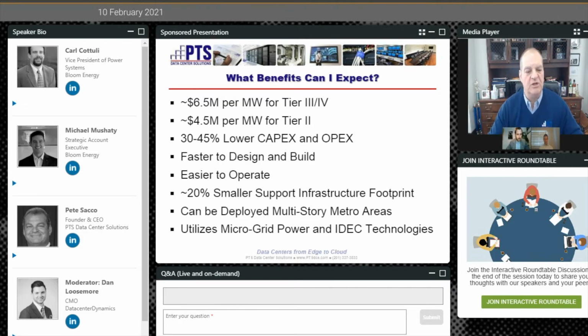As I mentioned earlier, you have a 20% smaller support infrastructure footprint, which is now predominantly outside the envelope of the building. This doesn't introduce further risk of having technicians who shouldn't be on the data center floor on the data center floor, and gives you greater capacity inside the building for the things that generate money — the IT, racks, and cabinets. You could deploy it at any density. I think one of the biggest attributes is that I could deploy it in a multi-story building, meaning it's suitable for a metropolitan area, because it uses external outside technologies for microgridding and indirect evaporation.